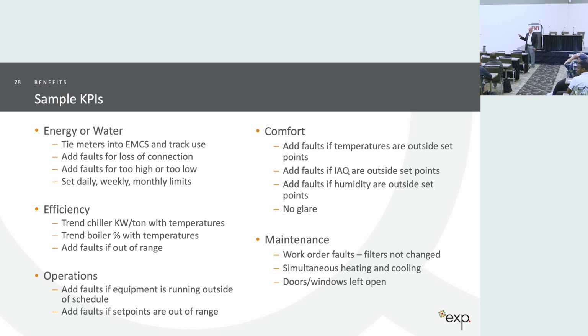And then looking at equipment efficiency: chiller kW per ton based on temperatures, boiler percentages of operation efficiency, and faults if anything's out of range. And that was where we were talking about the motor. If something gets out of the range we initially set up in commissioning, then we get a fault. Operationally, if something is running after a schedule, let's say it's running 24 hours, you can have a fault. The building operator might know, or they might not know. Somebody might have come by and accidentally hit the hand switch on a piece of equipment. Well, now it's running 24/7, and that's going to affect your utility bill. You want to know that before that bill comes to the C-suite.